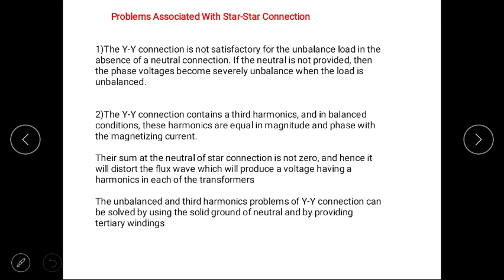There are some problems with star-star connection. First, star-star connection is not satisfactory for unbalanced loads in the absence of neutral connection. If the neutral is not provided, then the phase voltage becomes severely unbalanced when the load is unbalanced. It means if in the system there is no neutral and the system is unbalanced, then the output is also unbalanced, which may affect the load.